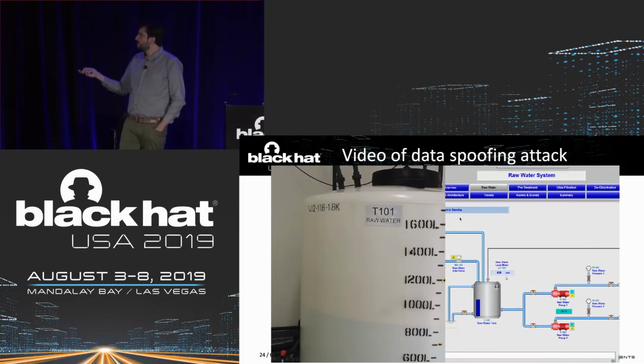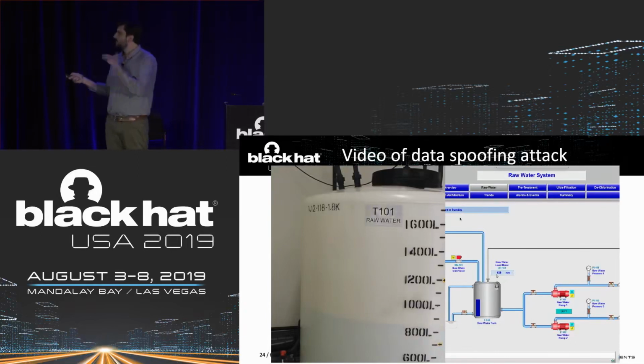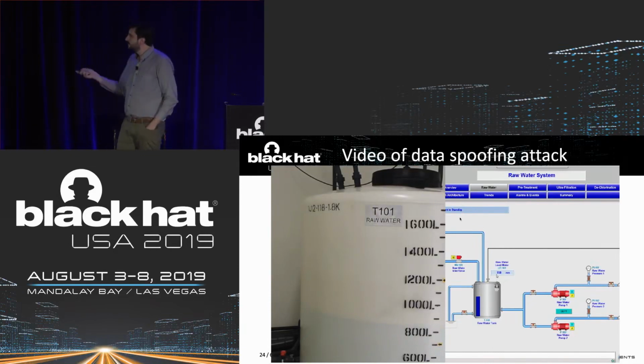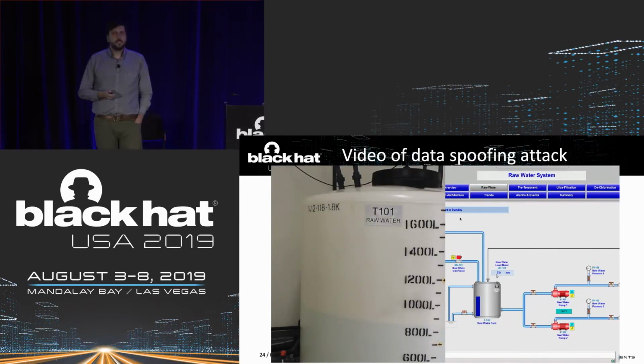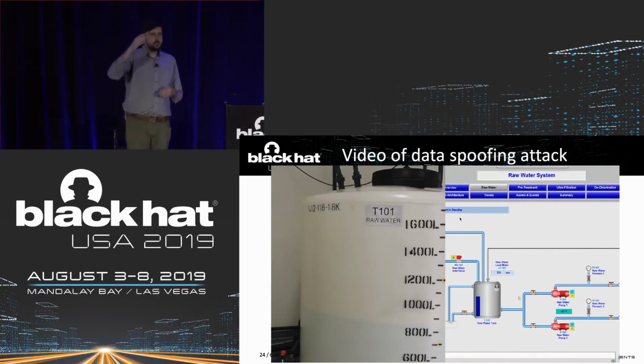Here we're spoofing the value, we close the valve, and we're still spoofing it—running a man-in-the-middle attack in parallel, constantly forging the values. At some point I'll stop the attack, and you'll see a sudden jump from 628 millimeters to 732 millimeters, because once I stop the attack, you see the real value. I can do this in many ways, from L0, L1, or SCADA—there are plenty of ways, but essentially they're all forging sensor data.